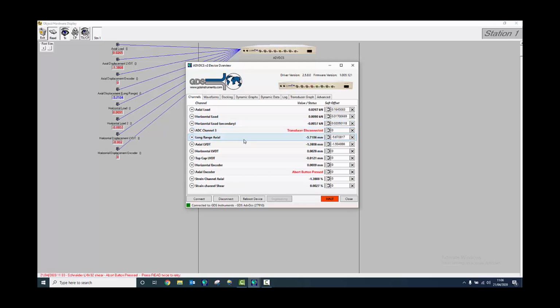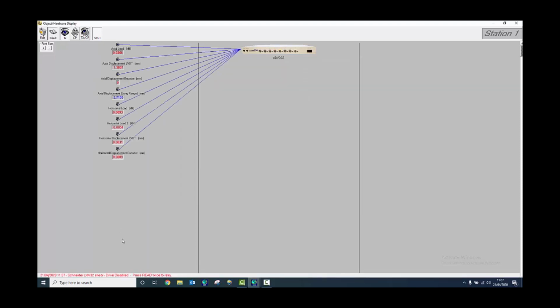To check the displacement transducers, we'll use the motor control because that is the safest way. The motors are set up and communicate with the acquisition system. To do that, we'll release the stop button, which will energize the motors. The machine should not be moving anywhere on its own. If you look at the screen, it tells you what to do. So the machine, because we had the abort button pressed, it saved some errors in the memory. But to clear them, you have to press read twice.